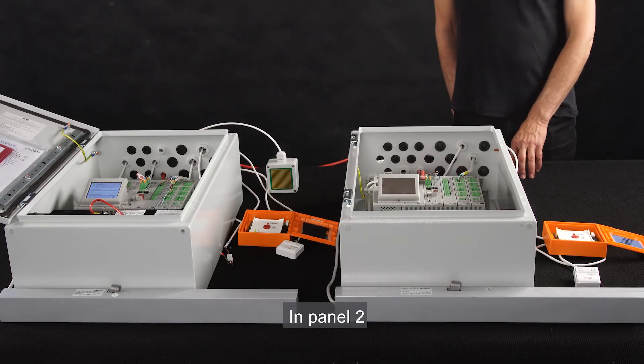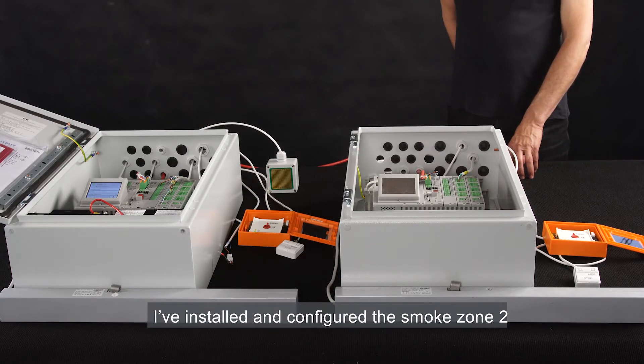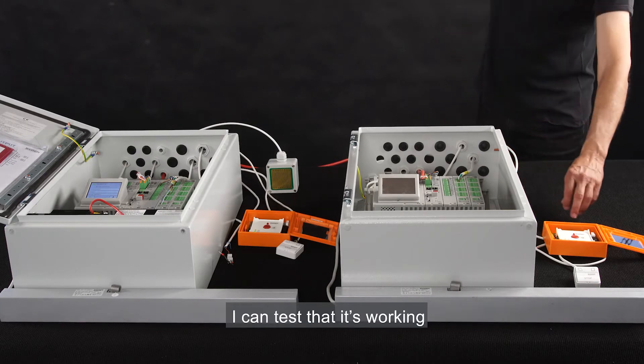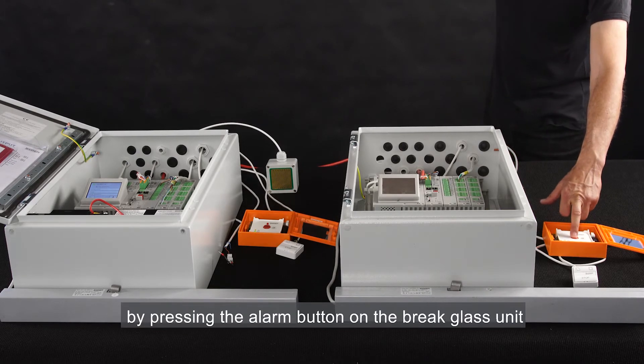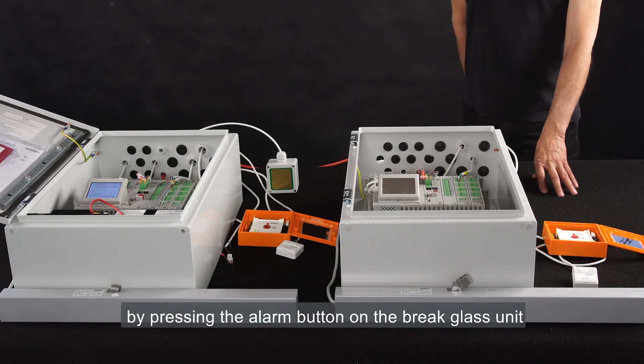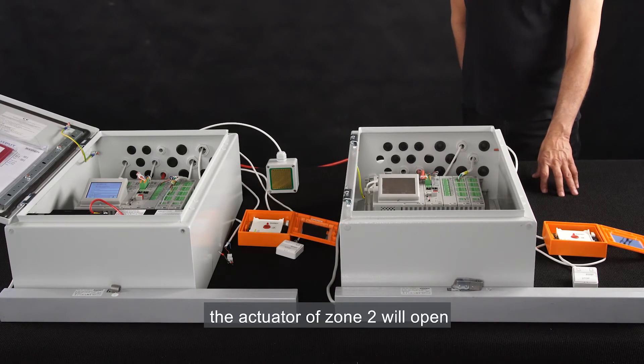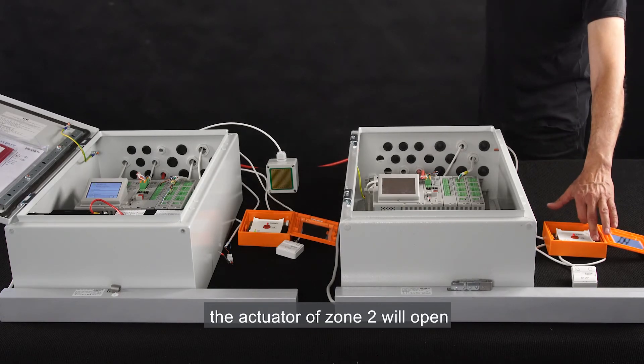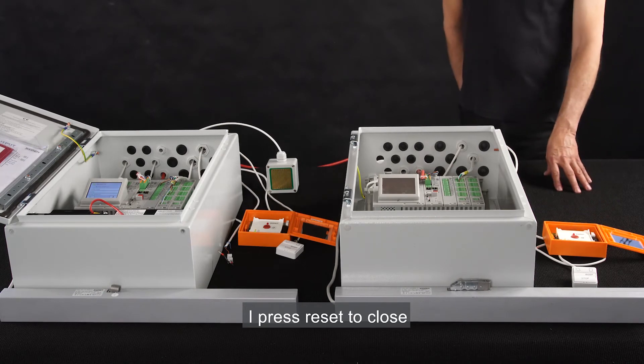In panel 2, I've installed and configured Smoke Zone 2. I can test that it's working by pressing the alarm button on the break glass unit. The actuator of zone 2 will open. I press reset to close.